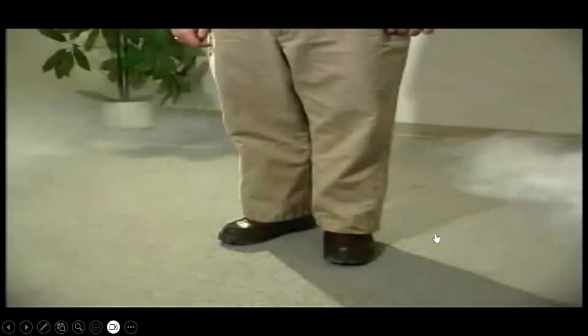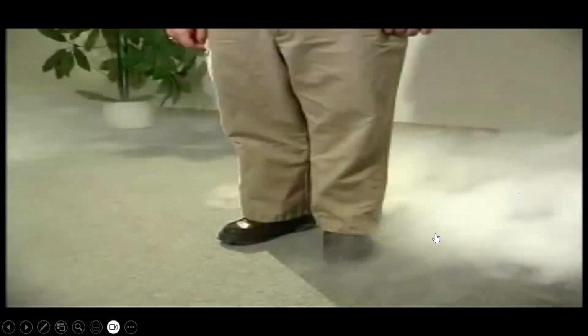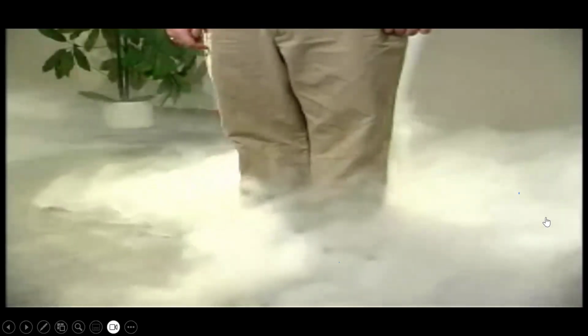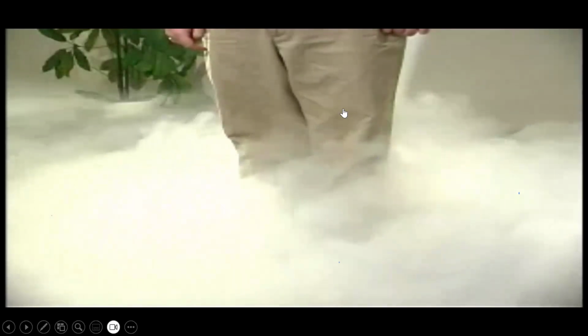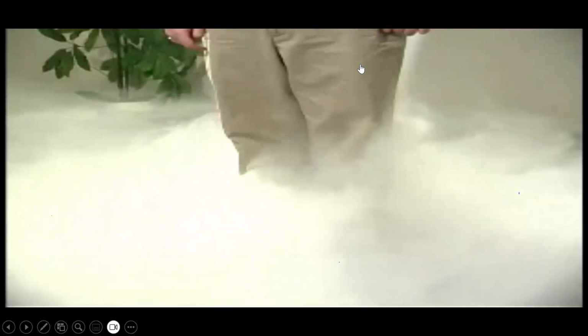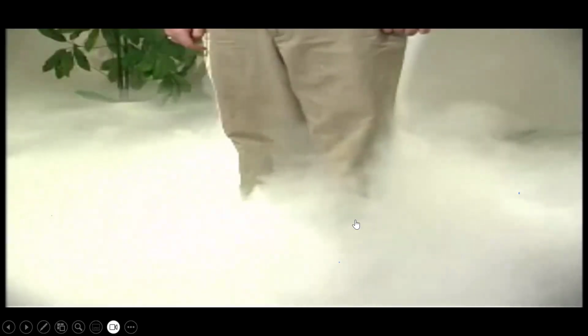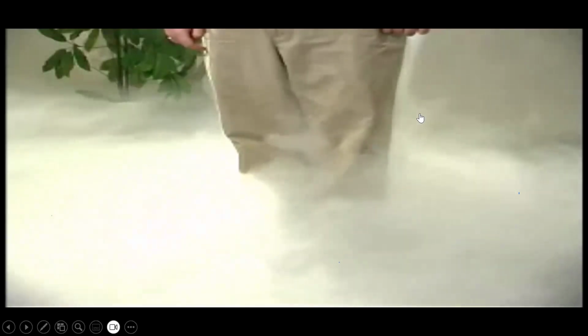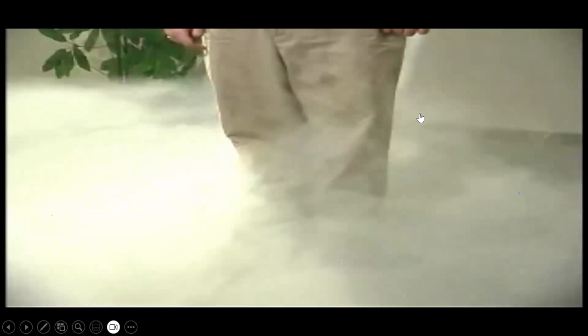So here you see a person, a human being like you and me, and there is that air at about 68 to 70 degrees Fahrenheit. As it encounters a person here, it starts to get warmed and it will start to rise up. Now imagine that this cool filtered air enters the space, and you can see the thermal plume being created, and it comes into your breathing zone. It is not mixing with the room air. So the quality of air that you get is much better than what you would get in a mixing air system. That is why we are saying that the ventilation effectiveness in a displacement system is approximately 17% less air is required. We say the ventilation effectiveness is 1.2.